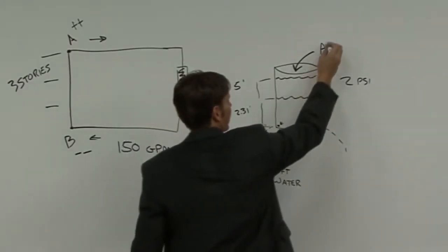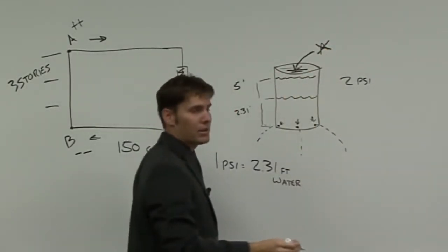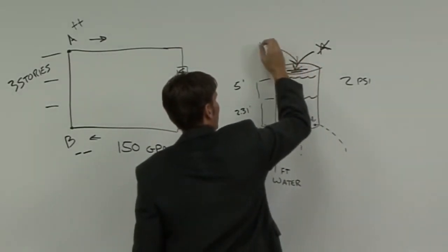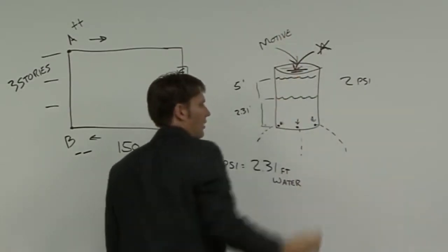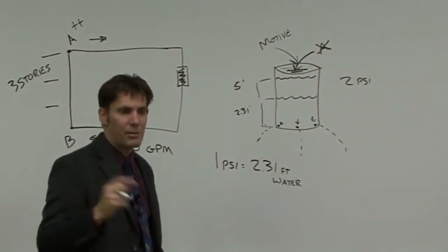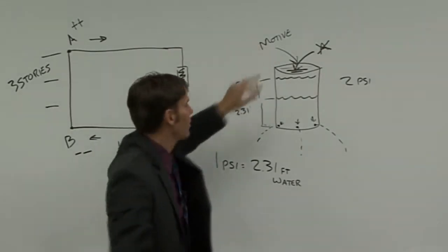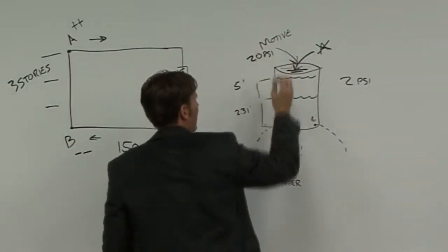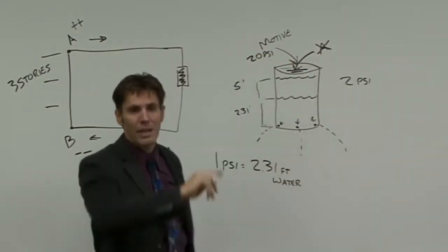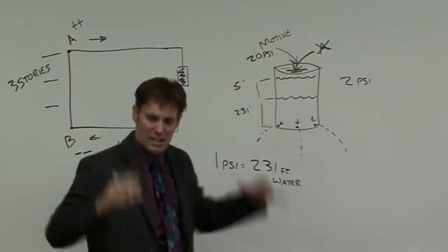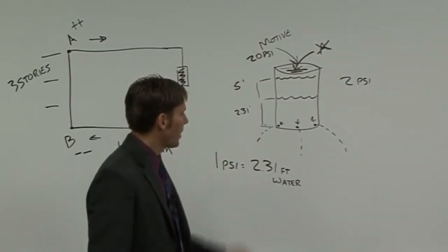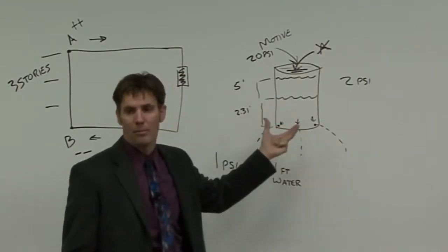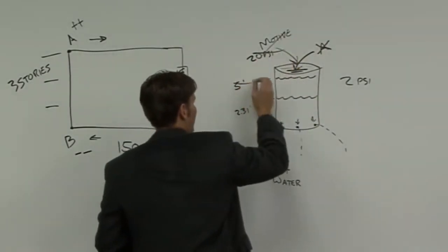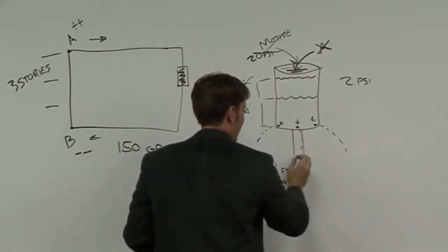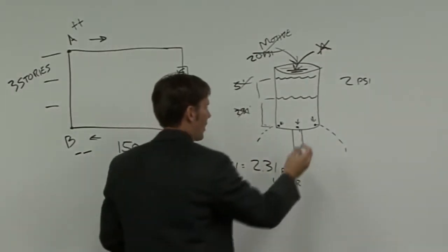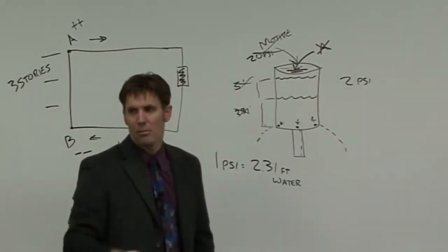Another option is I could seal this can from the atmosphere, and I could provide it a motive force, a motive pressure, maybe compressed air. We do this with steam in condensate return applications. We provide something that's at a higher pressure. We could provide a 20 psi motive pressure, and suddenly I've got a lot of pressure, and now I'm getting everybody in the room wet because I'm really pushing it down with the pressure. Well, this is a great example of how a centrifugal pump is going to work. If we eliminate these options and I mount this can on a rotating assembly, I now move this in a centrifugal motion. I spin it.